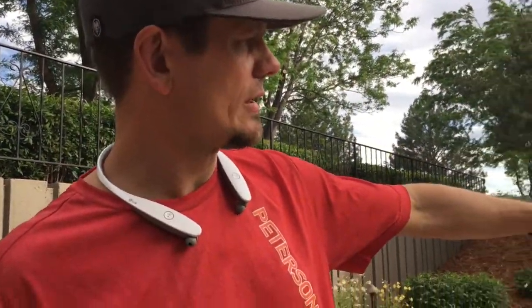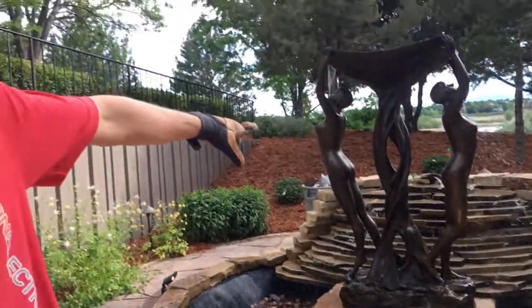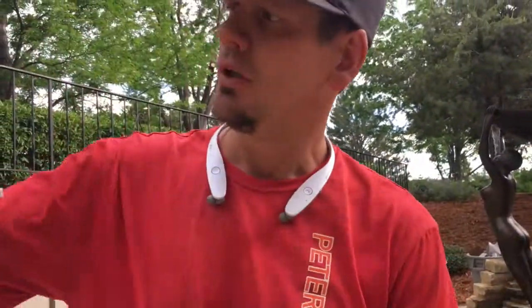If you're having a hard time figuring out where that goes, remember that when the neutral dies on a GFCI, it doesn't have continuity back to your panel — that's a pointer that might help you. They've got a little manhole over here that they've already covered up, but that helps you know that's what goes to the fountain and back over to here. Thanks for joining us.